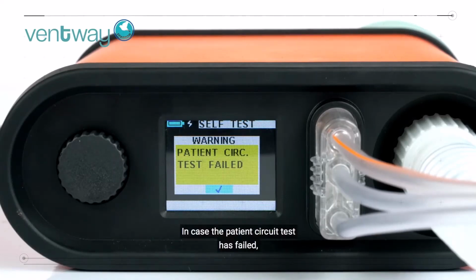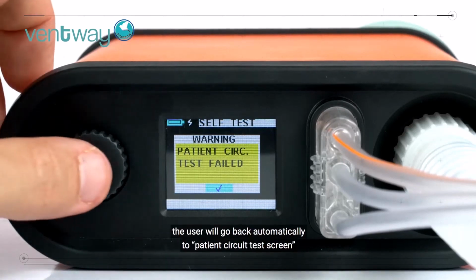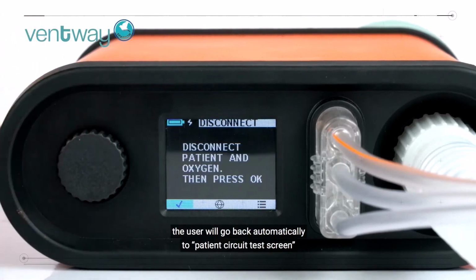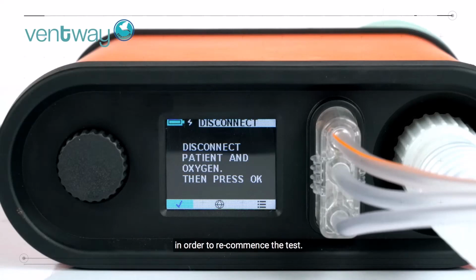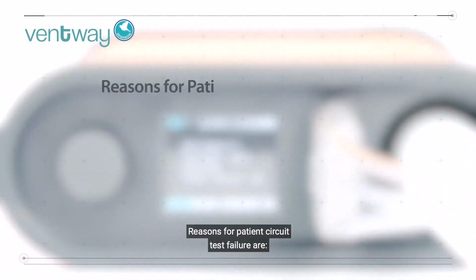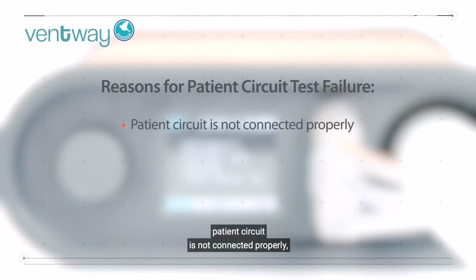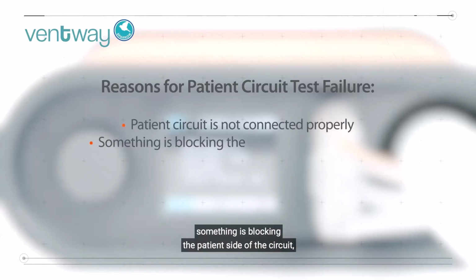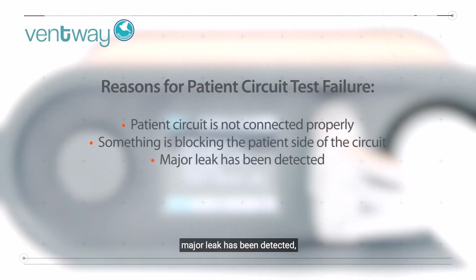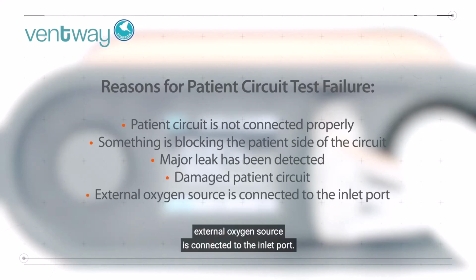In case the patient circuit test has failed, a test failure warning will appear. By acknowledging it, the user will go back automatically to the Patient Circuit Test screen in order to recommence the test. Reasons for patient circuit test failure are: patient circuit is not connected properly, something is blocking the patient side of the circuit, major leak has been detected, damaged patient circuit, external oxygen source is connected to the inlet port.